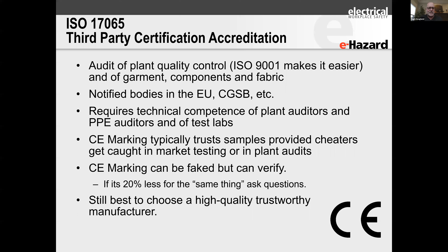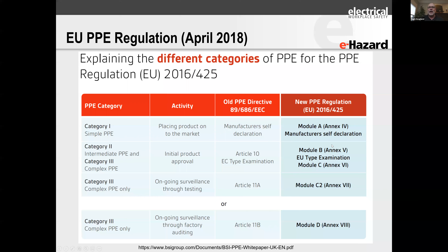Our laboratory is an ISO 17025 accredited lab. You want to make sure your data comes from that. If it has a CE mark, it has to have laboratory data—unless it's faked—and you can ask for that data if you want. With CE marks, the great thing is you actually have a 17065 accredited body who certifies arc flash PPE, level 3. So the garment is certified and the plant is certified. It's a fairly rigorous process, not quite as rigorous as the US third-party certification in NFPA for firefighting, but it is much better than our arc flash standard. So look for that CE mark from a reputable lab, and you'll get pretty good compliance. This is the EU regulation I just included.